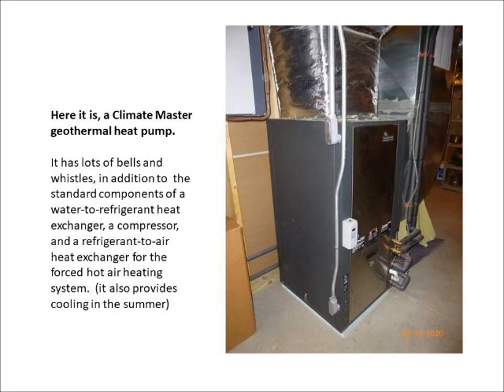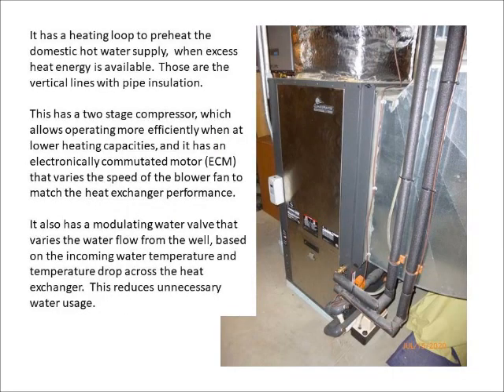Here it is, a Climate Master geothermal heat pump. On the outside, it looks very similar to a furnace. It's got lots of bells and whistles, in addition to the standard components of the water to refrigerant heat exchanger, a compressor, and a refrigerant to air heat exchanger for the forced hot air heating system. And as explained previously, the refrigerant loop can be reversed to provide cooling in the summer. It has a heating loop to preheat the domestic hot water supply when excess heat energy is available. Those are the vertical lines with pipe insulation.